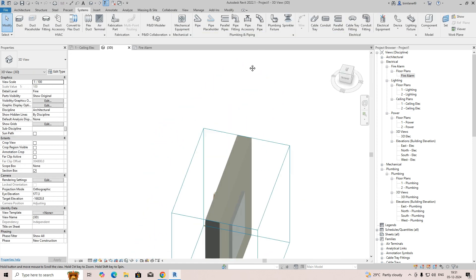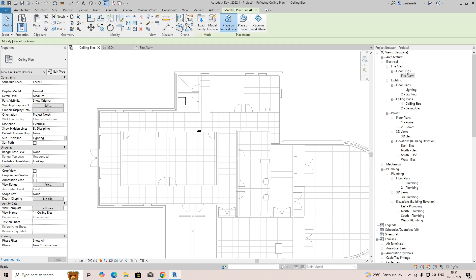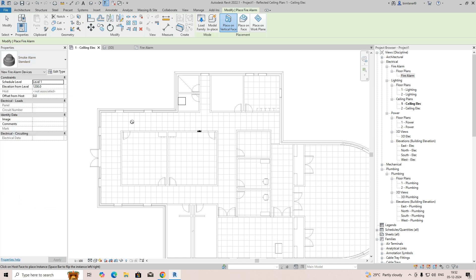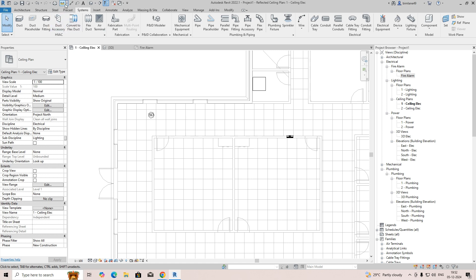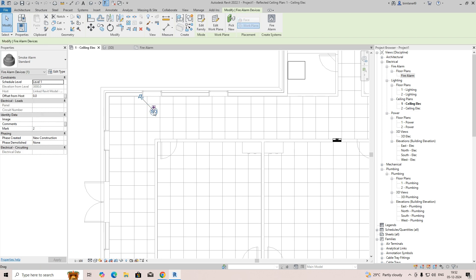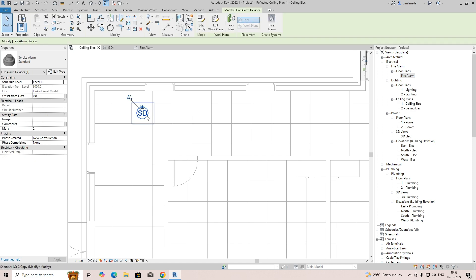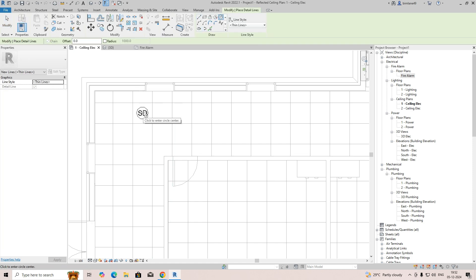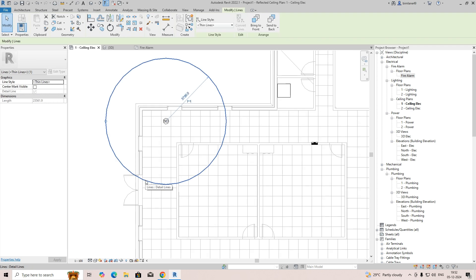Now we can place smoke detectors. Go to fire alarm and load the standard smoke detector family. Select 'place on face' and fix one fire alarm device here, maintaining some gap from the wall. For coverage, give a radius of 3500. Go to Modify, type DL, take a circle, center it on the detector, and make the radius 3750. This represents the coverage for one smoke detector.